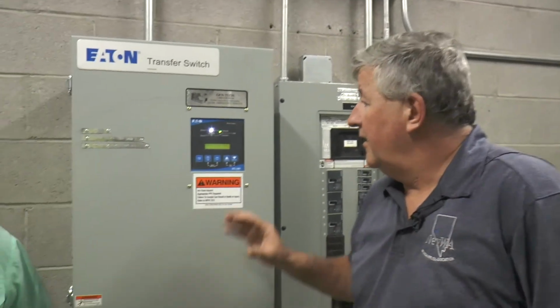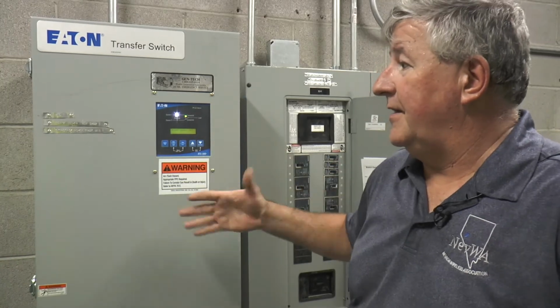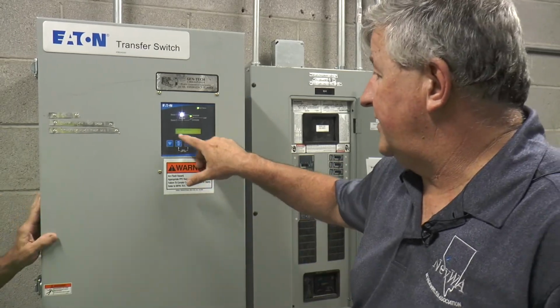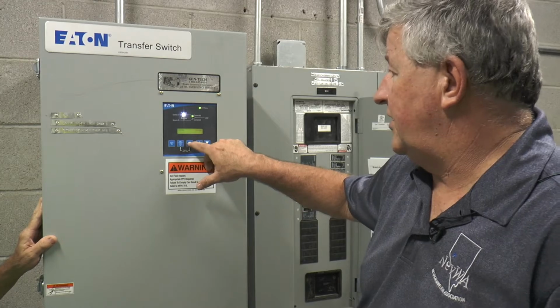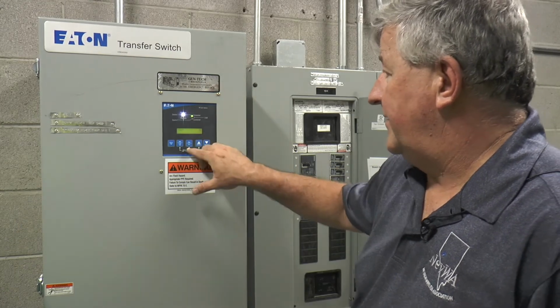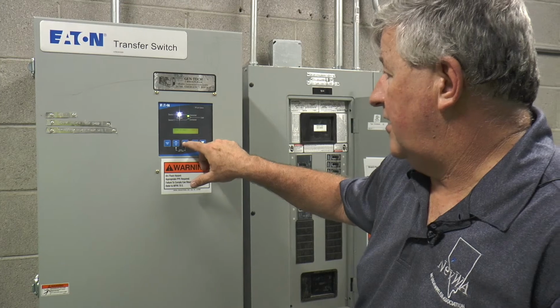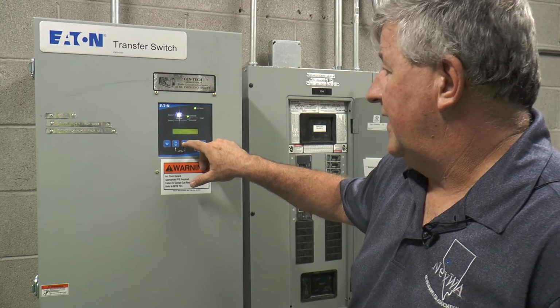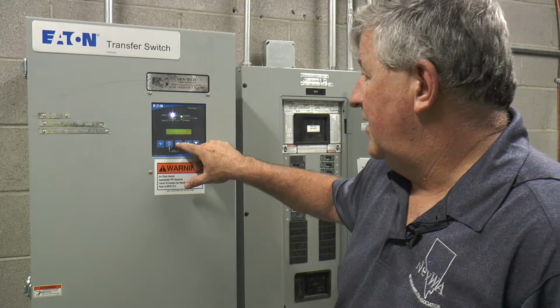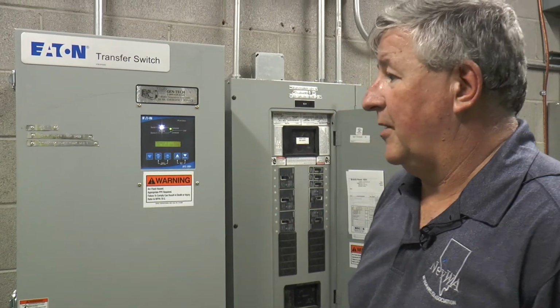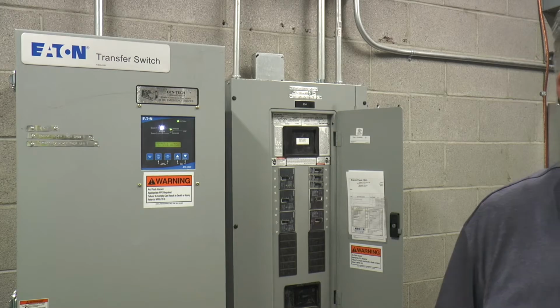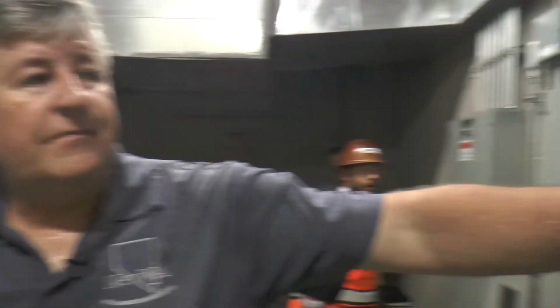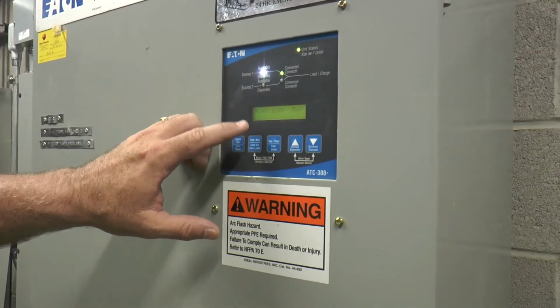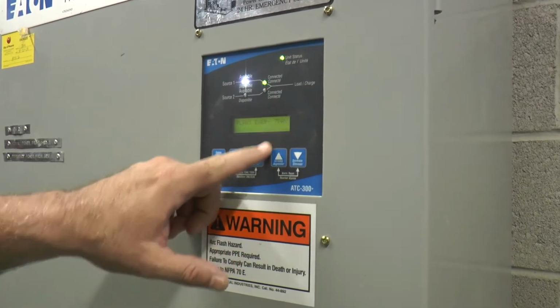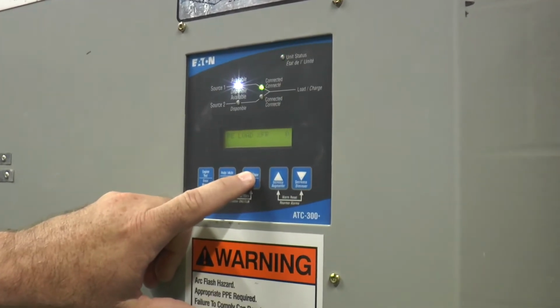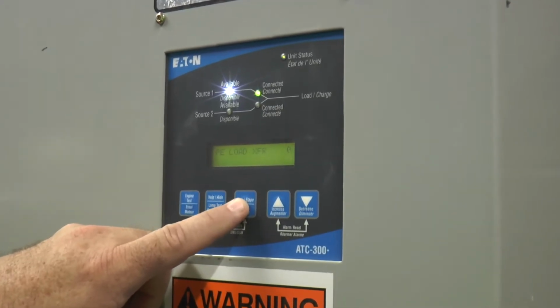It makes no difference. Each switch has its ability to start and stop the generator set via an exercise, test mode, duration, pre-transfer. Basically, that's it. Once it gets all the way through, language, change time and date, no, reset, no, we're back to normal. Then on this switch, we'll look at the plant exerciser. The controls are still identical. Right now it's on a 7-day exercise. It's a no load transfer, 0, so it's just going to start the generator set.